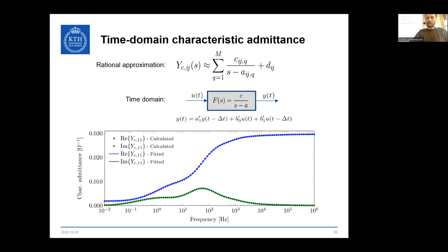However, since the difference between internal and external fault is only going to be transient, in order to actually detect something, you calculate the slope of the wavefront, basically saying that a fault beyond this reactor on the remote side will have a slower wavefront than the internal one.